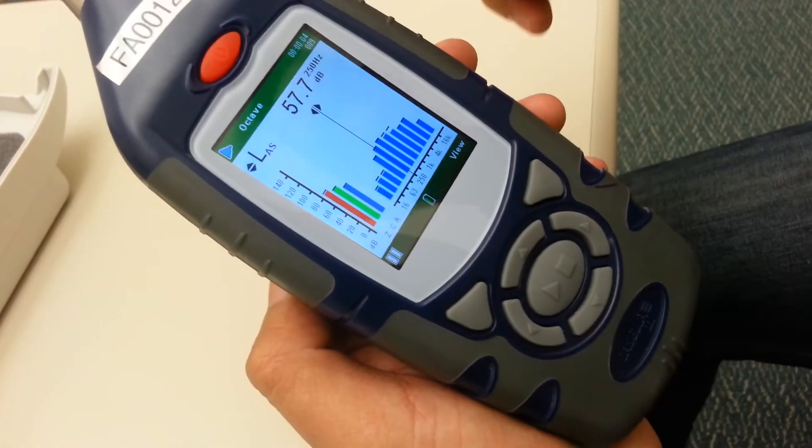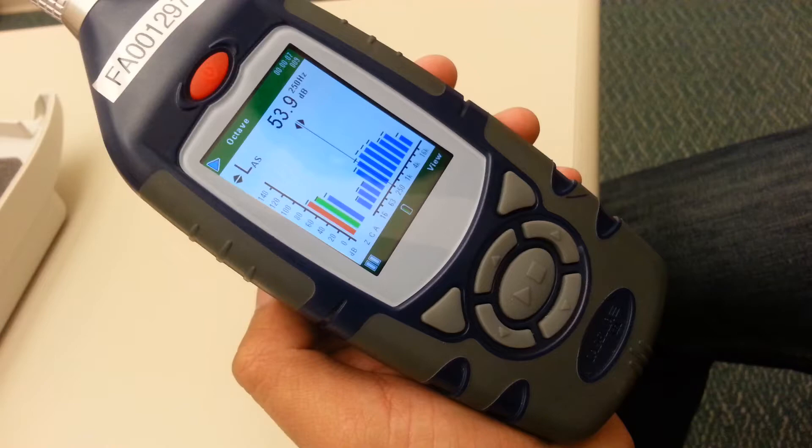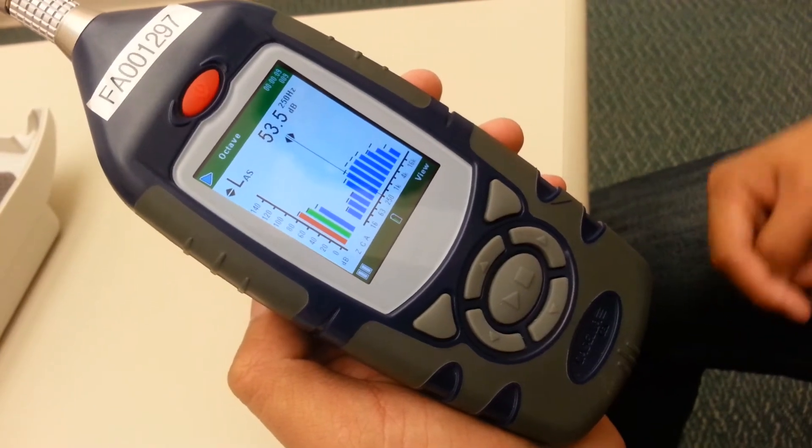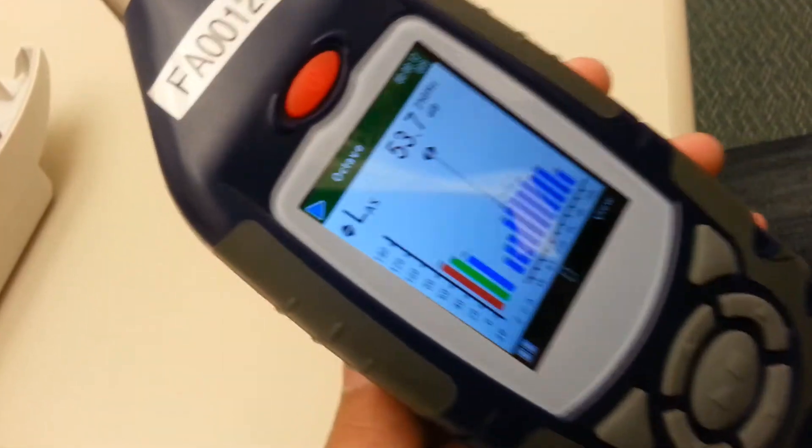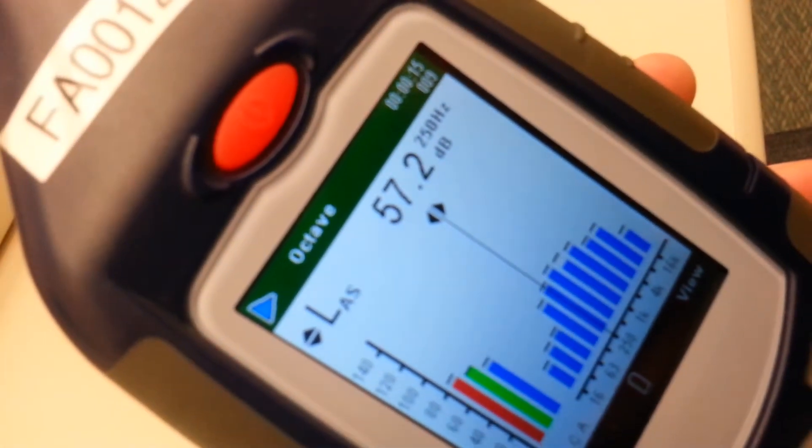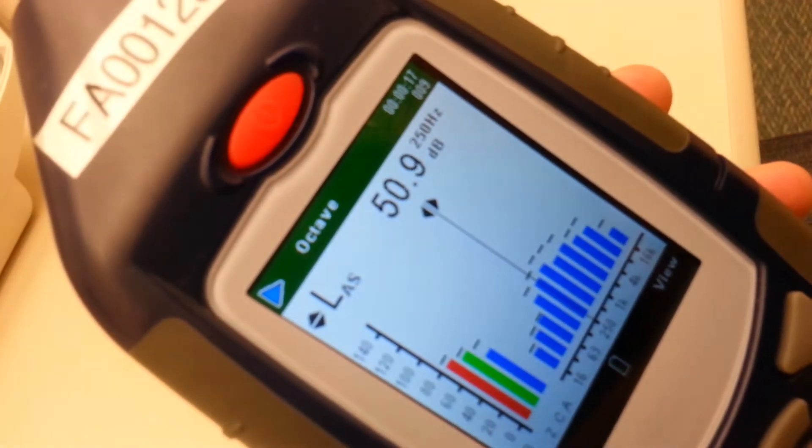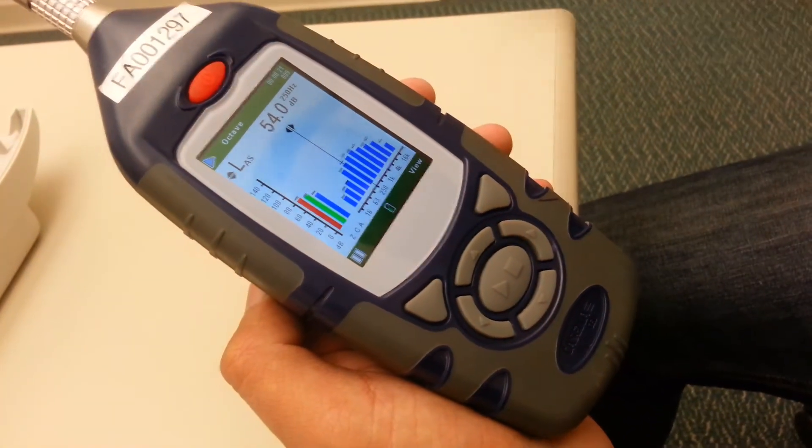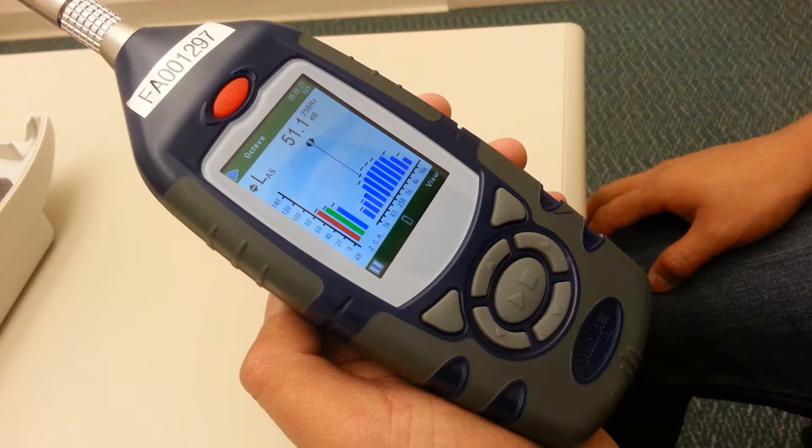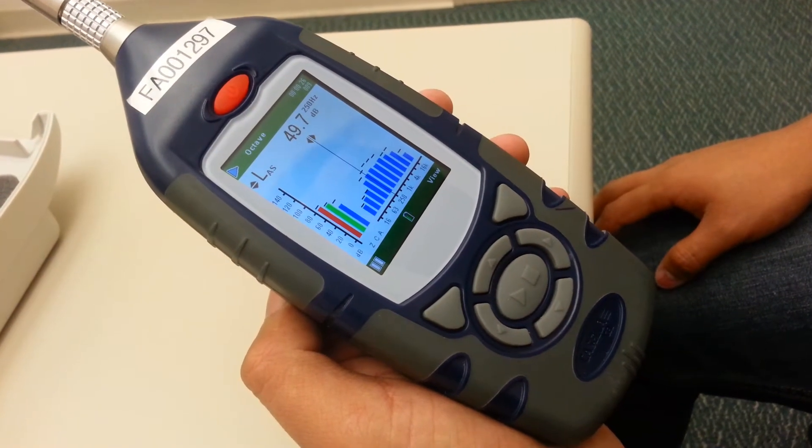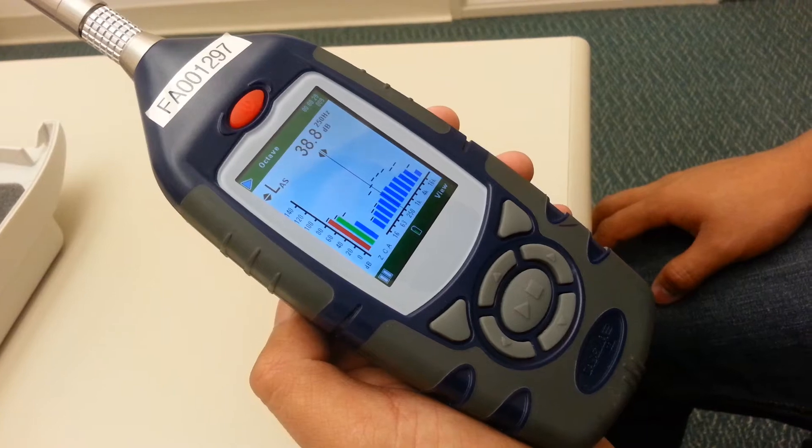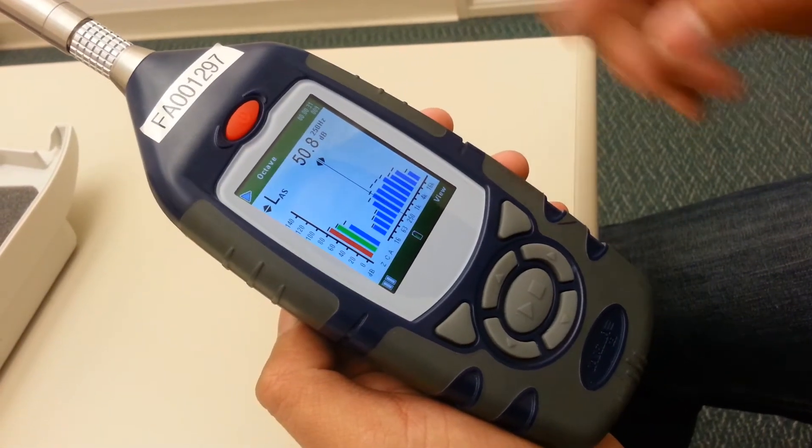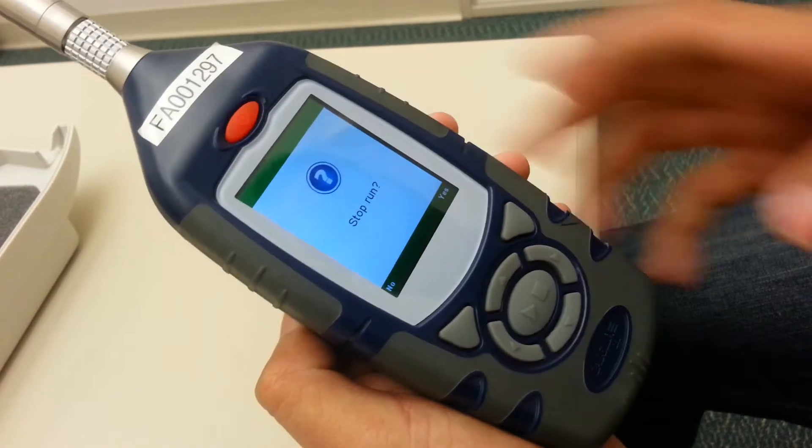You'll notice in the upper right hand corner that there's a timer going. And it will go until two minutes and then start back at zero. Right when it hits two minutes, we want to press the stop button. This will log the data and the average LEQ value for the two minutes. We can stop this early by pressing this.